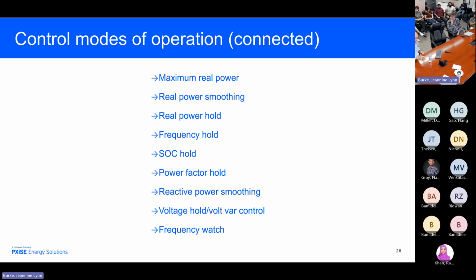Now, the last one, called frequency watch, we've implemented that in Guam. That has saved them an innumerable amount of outages due to under-frequency relay trips. Frequency watch is simply when the frequency gets out of bounds, you blast it with the microgrid to arrest that sudden descent. The df/dt comes down real fast. The quicker you can hit the grid with real power, the slower you're going to hit that, and it won't hit the trip point on frequency.